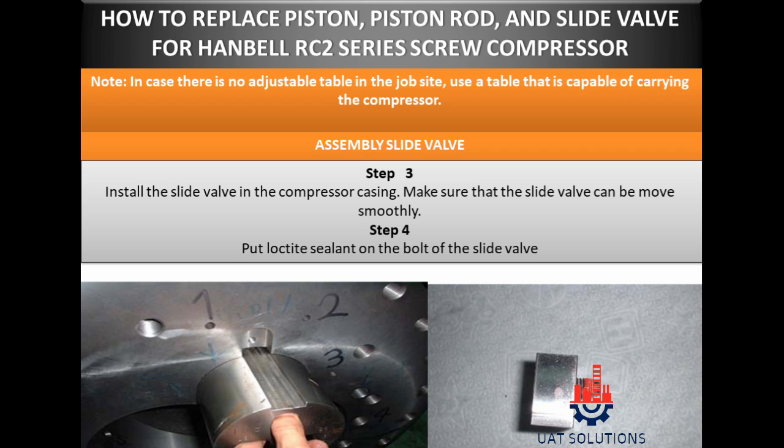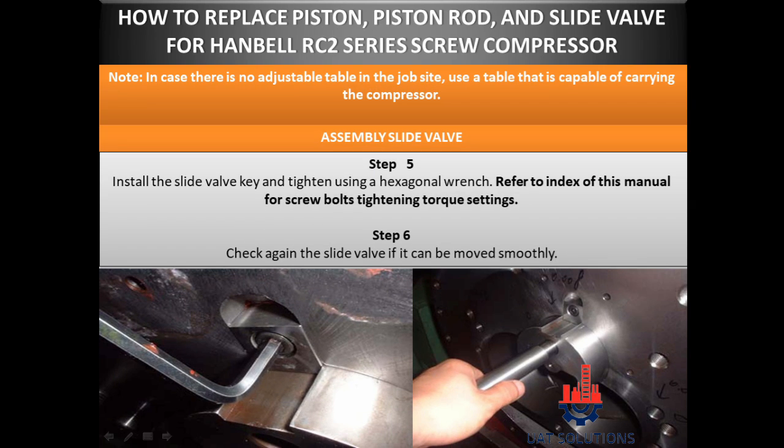Step 4: Put Loctite sealant on the bolt of the slide valve. Step 5: Install the slide valve key and tighten using a hexagonal wrench. Refer to the index of this manual for screw bolts tightening torque settings. Step 6: Check again the slide valve to confirm it can be moved smoothly.